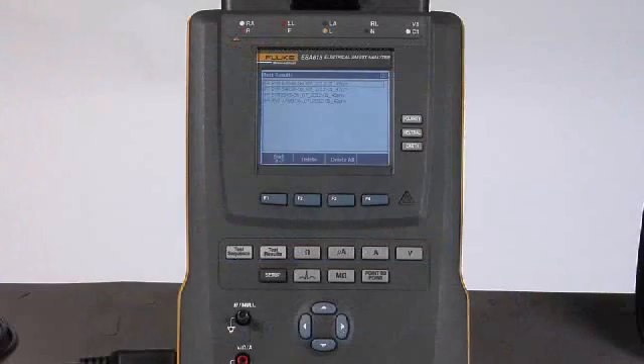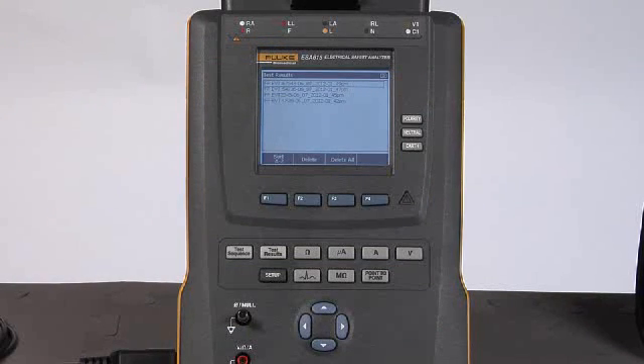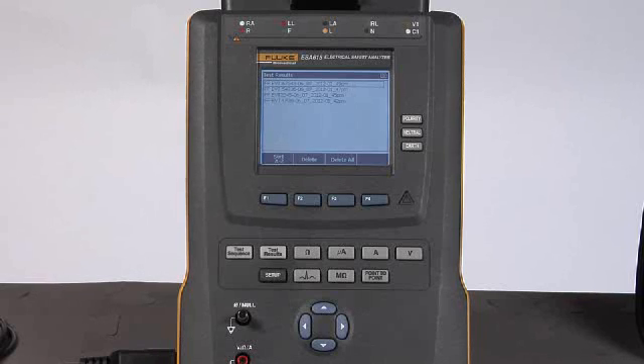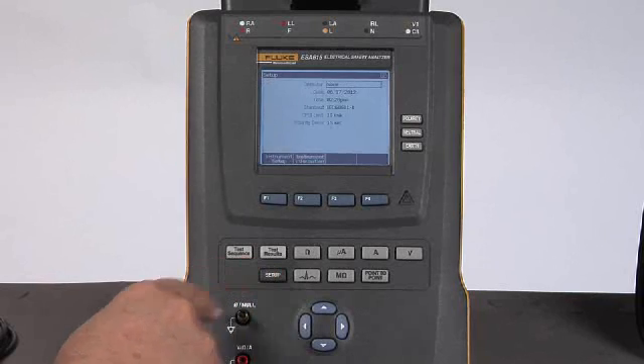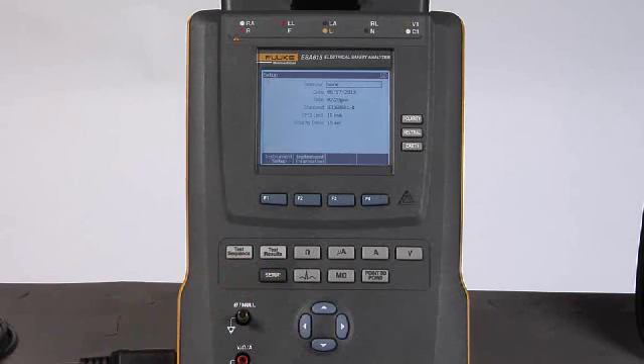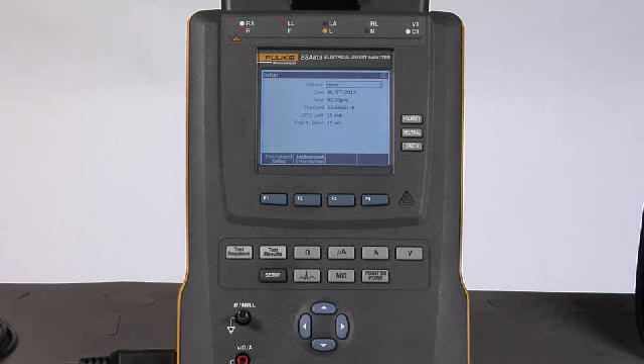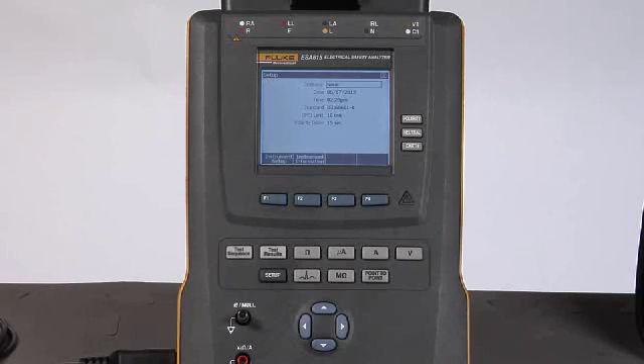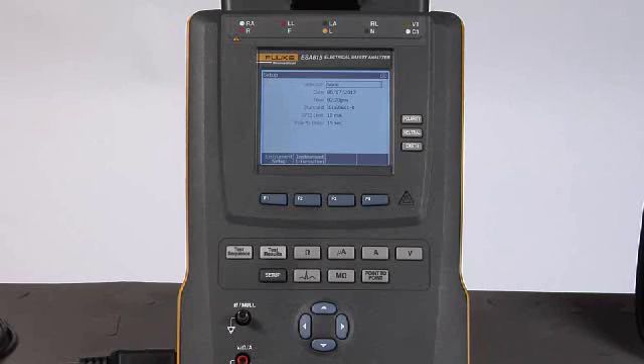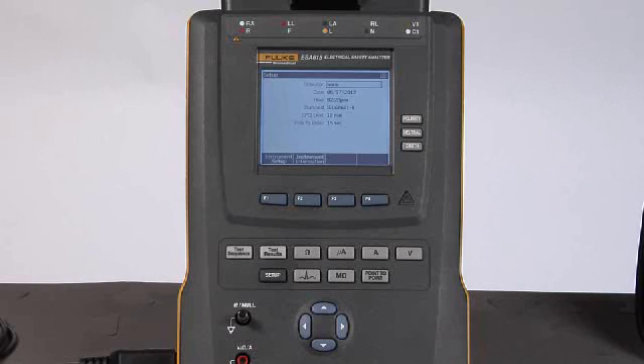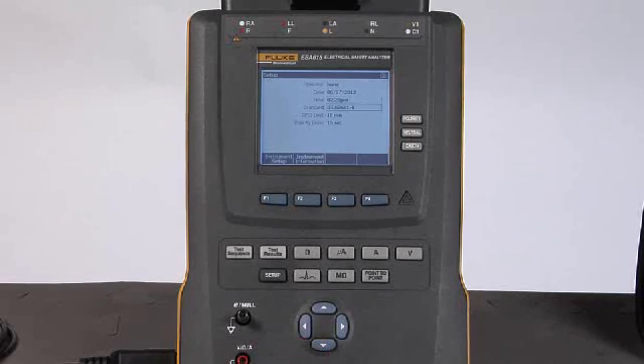The ESA615 can also be operated manually. And when I do that, it's important that I take care to ensure that there are a couple of settings that are properly made. I will press the setup button, and this allows me to select the operator or person who is going to be doing the testing. I can select myself or any others in the list, and I can have as many people in the list as I need. The other setting here that is really important to make sure that I select is the standard. And to get there, I just arrow down to the standard and press enter.